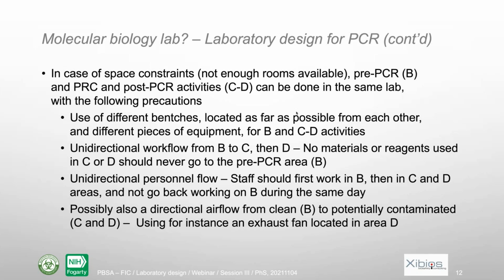However, in some situations, mainly existing labs, there are not enough rooms available for this. And in that case, if it's not possible to apply the best possible practice, you could conduct all activities in the same lab. But that has to be done with some well-defined precautions. Of course, you should use different benches in order to avoid any cross-contamination, and they should be located as far as possible from each other.